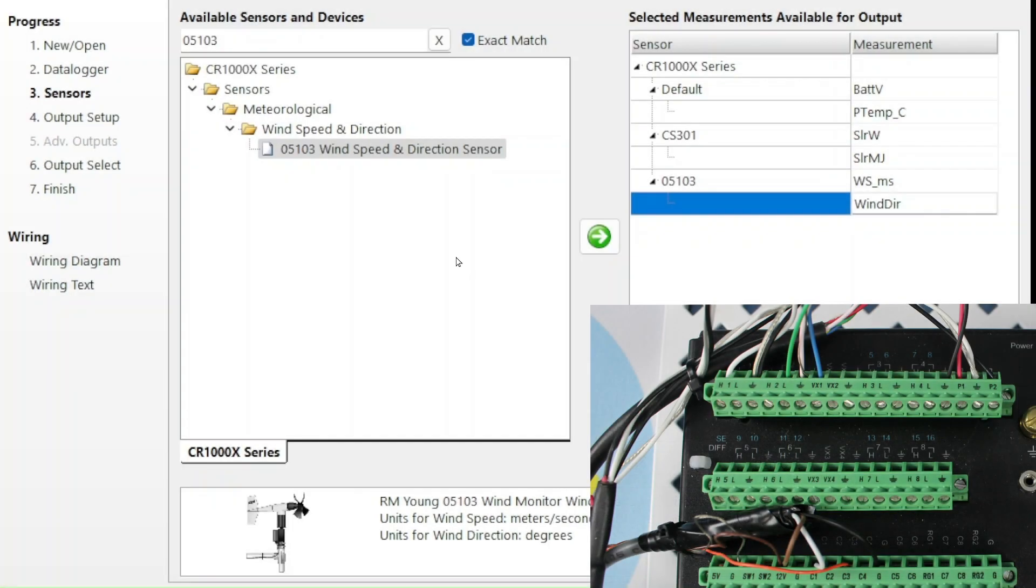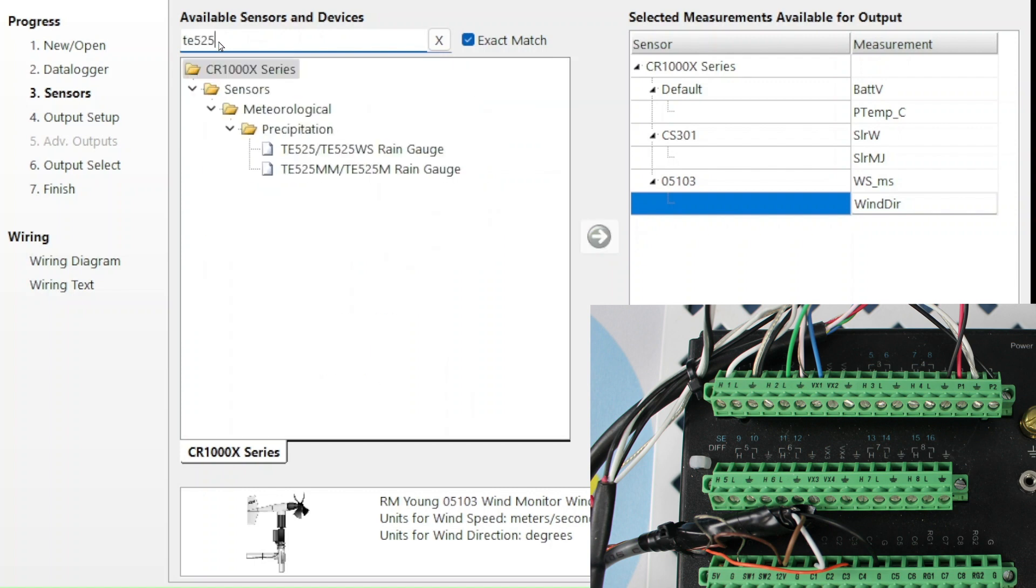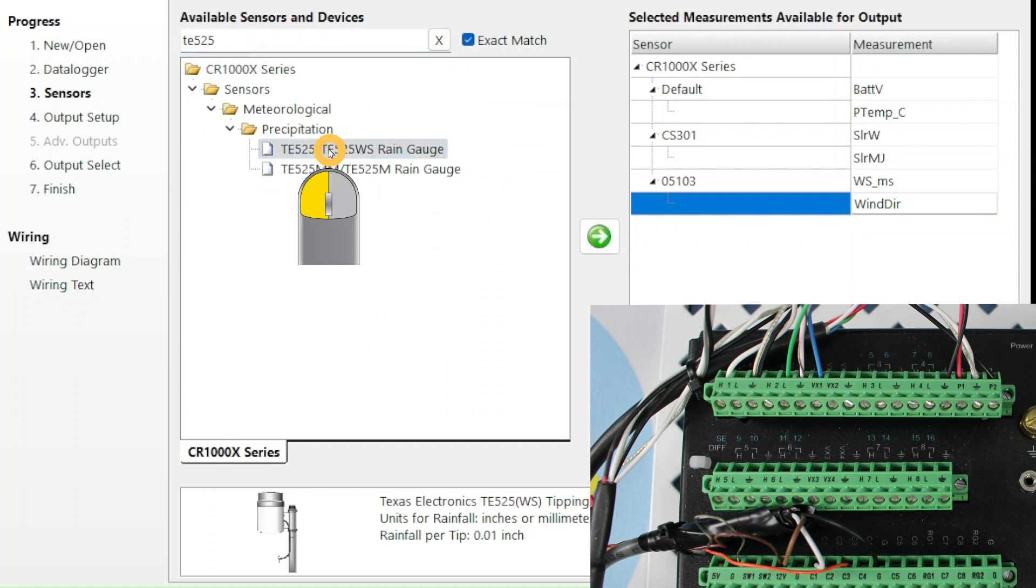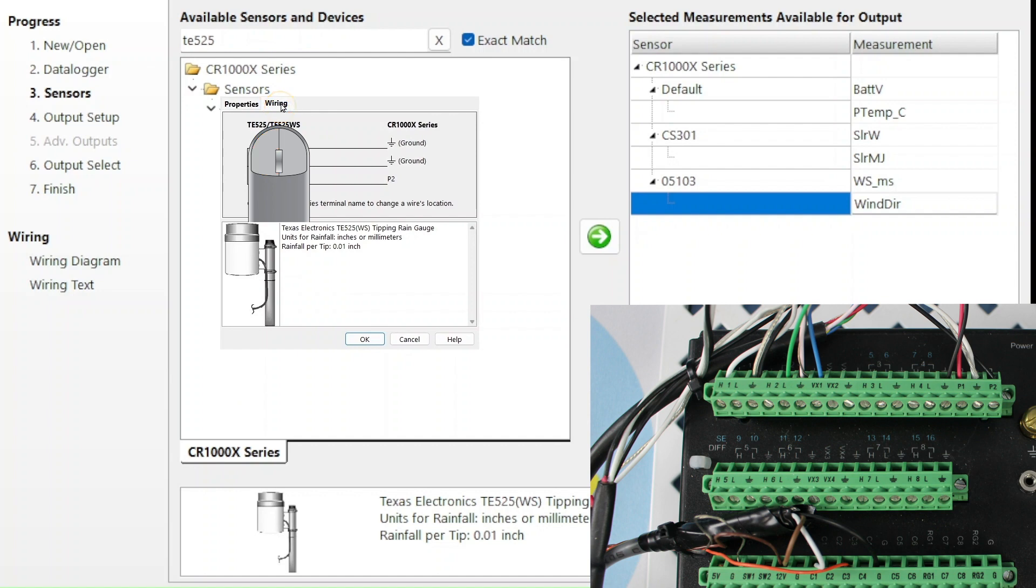The next sensor on my wiring panel is connected to P2 and ground. When I tried the TE525 earlier, SCWIN assigned the black wire to P1. Since that has been claimed for the 05103, SCWIN now assigns the black wire P2. Make sure the wires match the photo. They do, so I select OK.